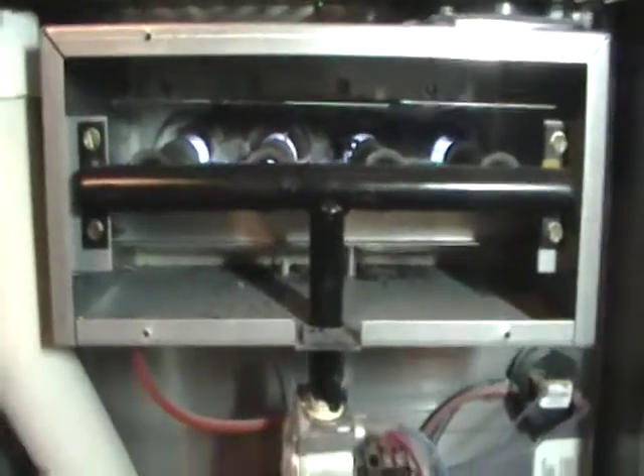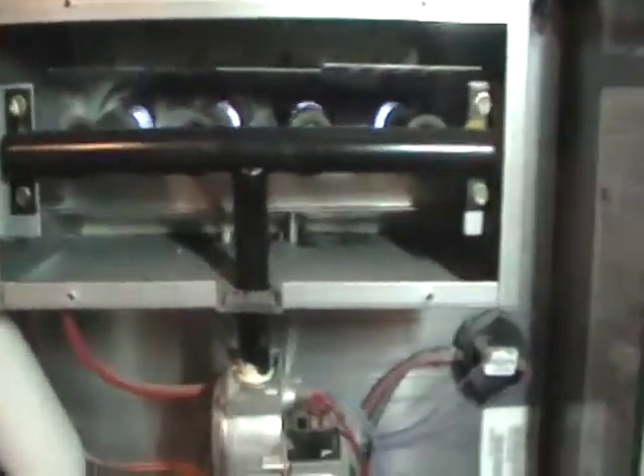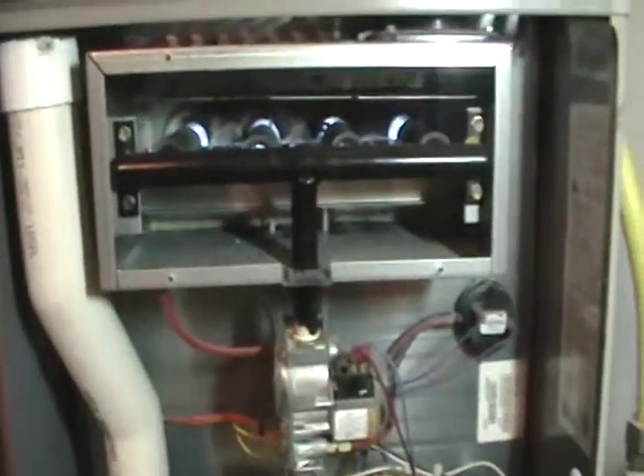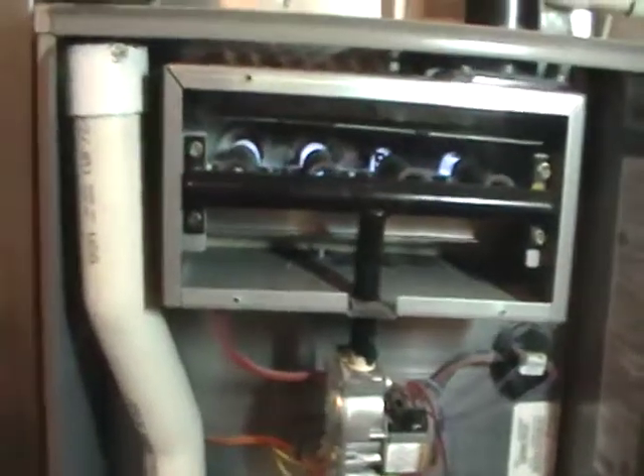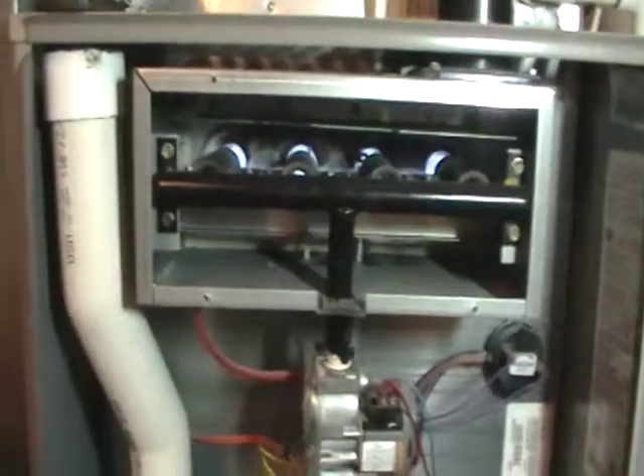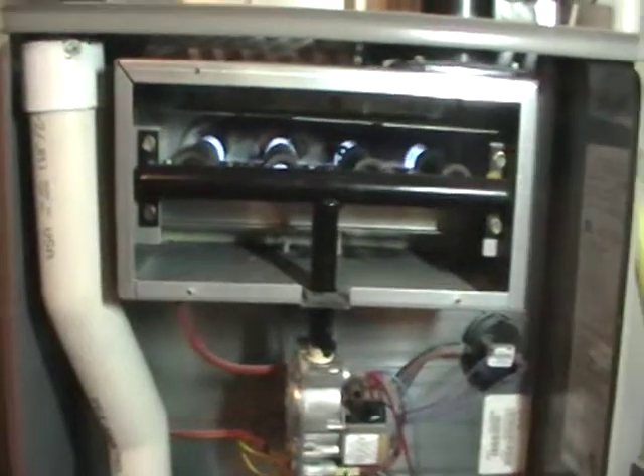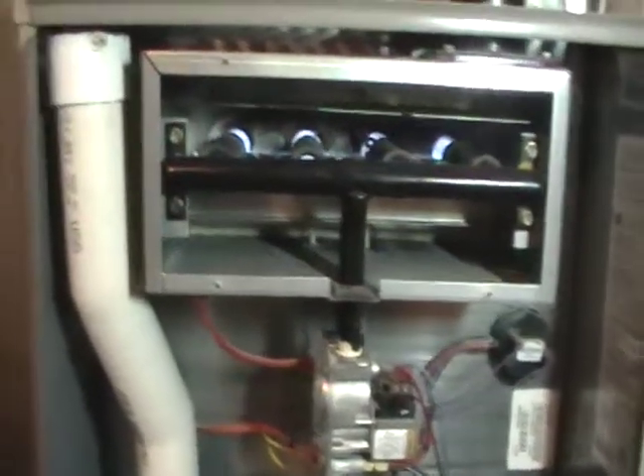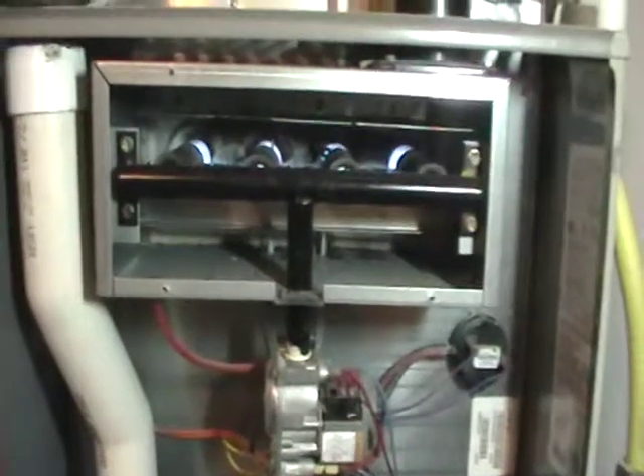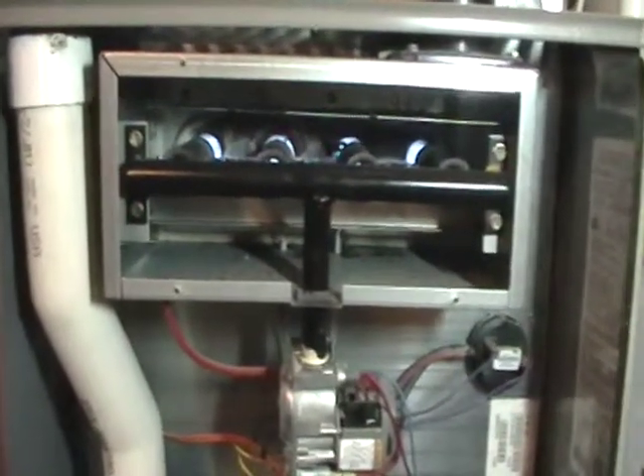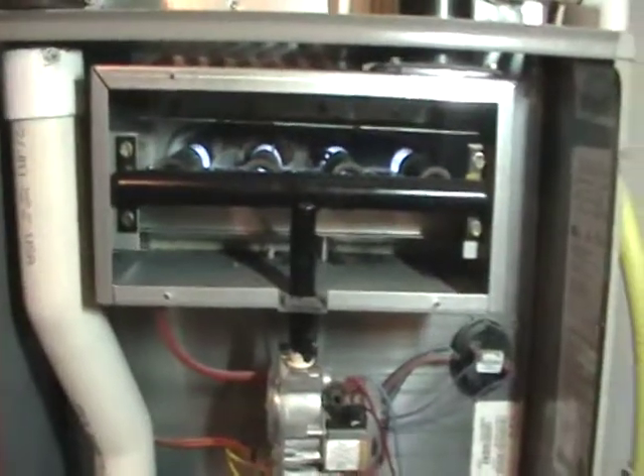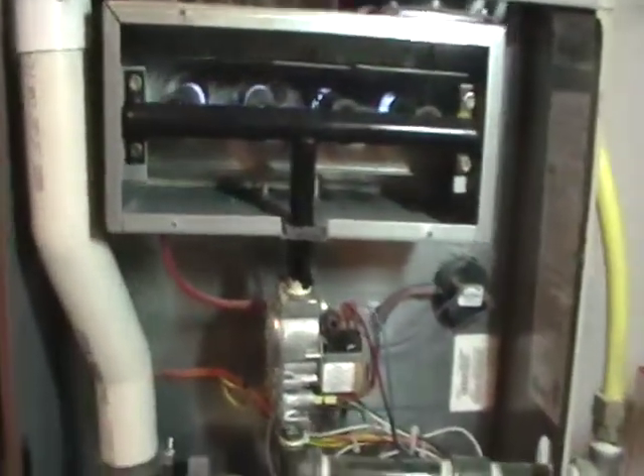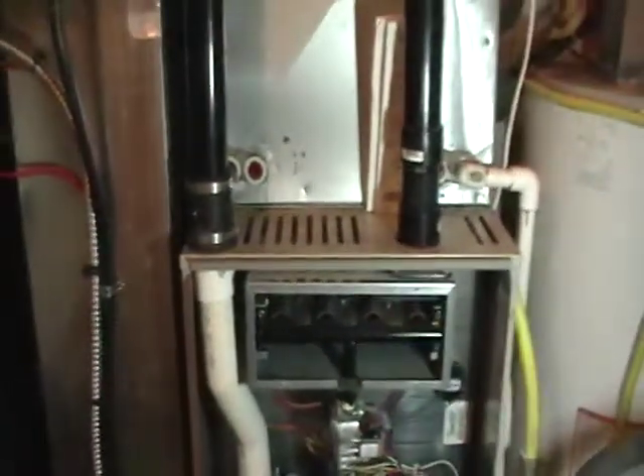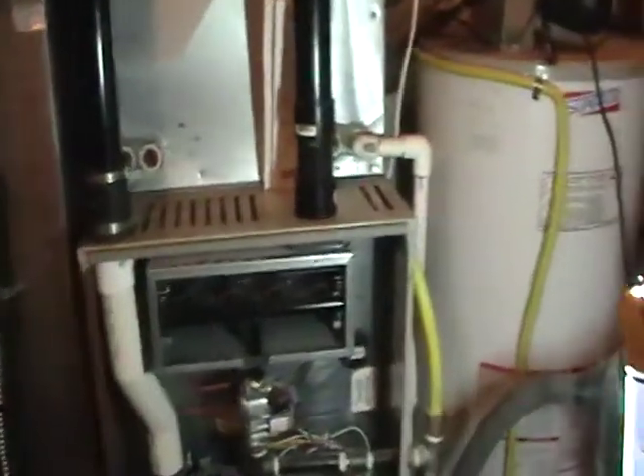I want you to remember that if you smell gas, see any signs of poor venting like black sooting or staining around the combustion chamber or draft diverters, call a professional. Poor flame characteristics as well require professional attention, and if there's any sign of heat exchanger corrosion or vent gases that can be smelled in the area or in the home, it can be a sign of a failed heat exchanger or other problems that require immediate attention, so call a professional. Carbon monoxide is a very real health concern, and a CO detector is always a great idea in the space or in the hallway adjacent.